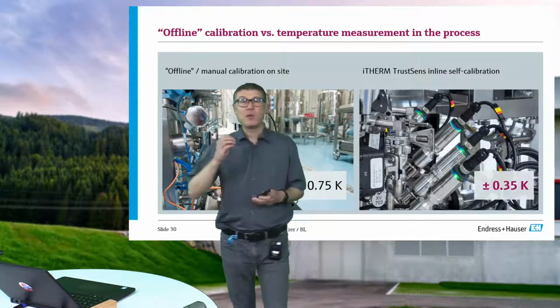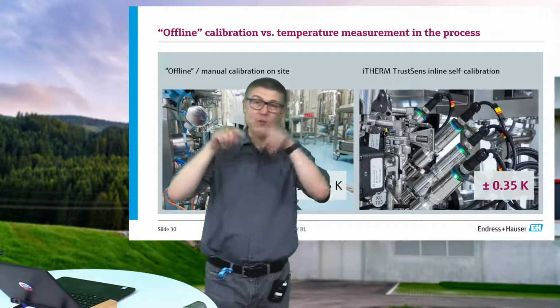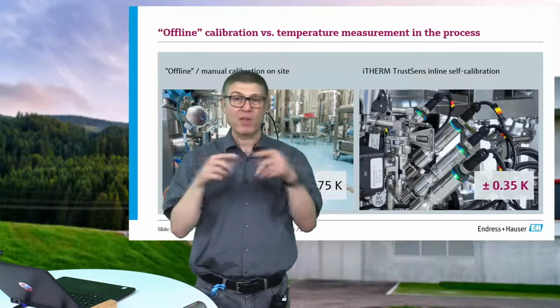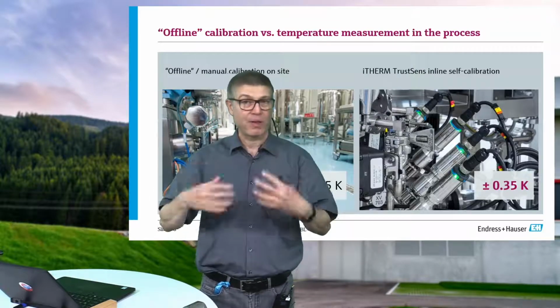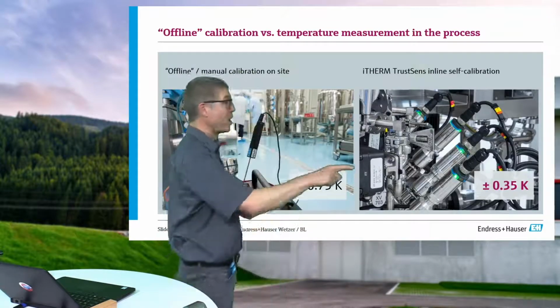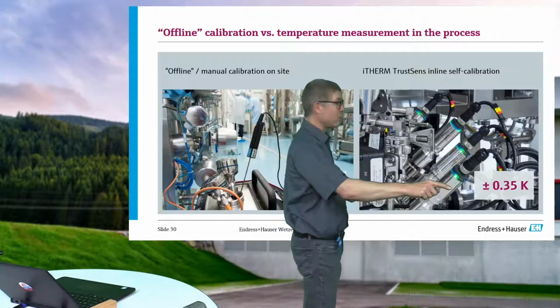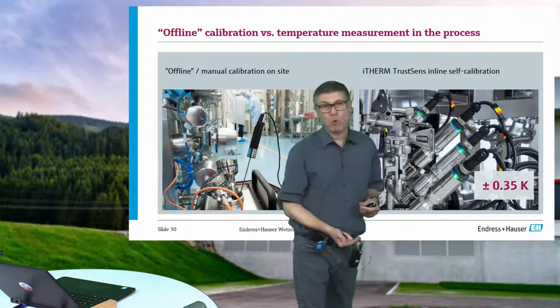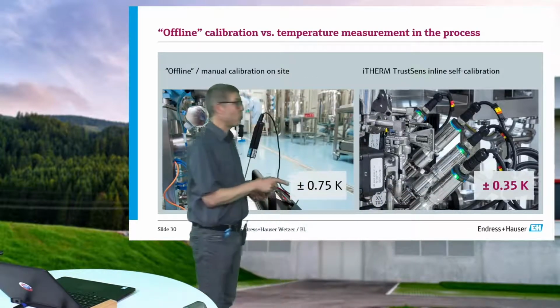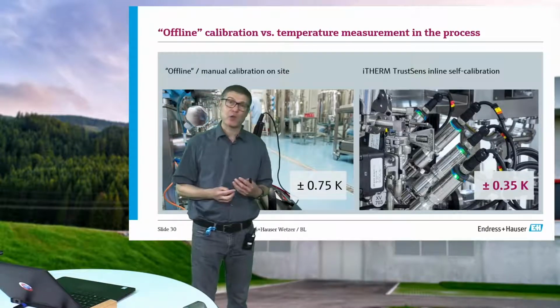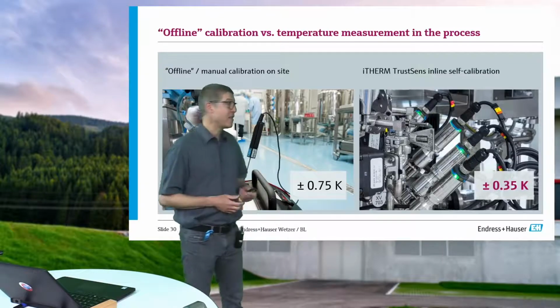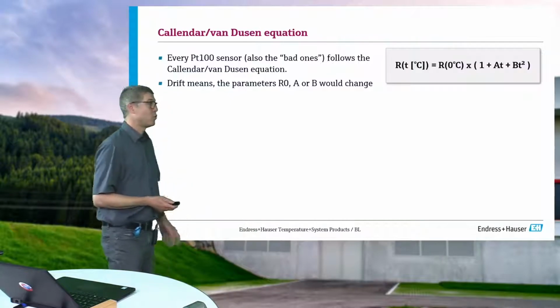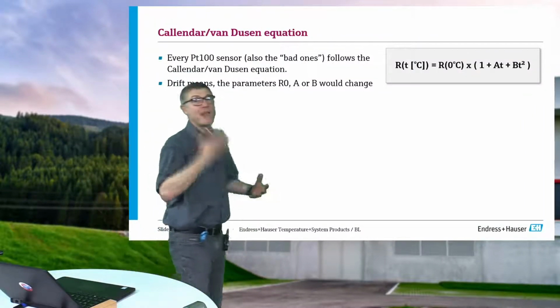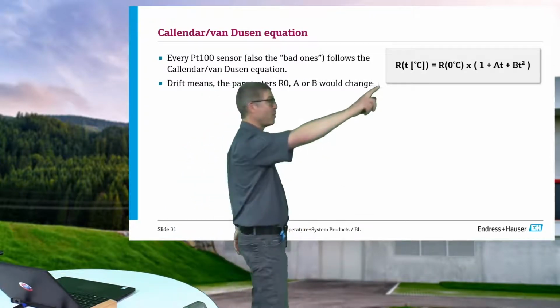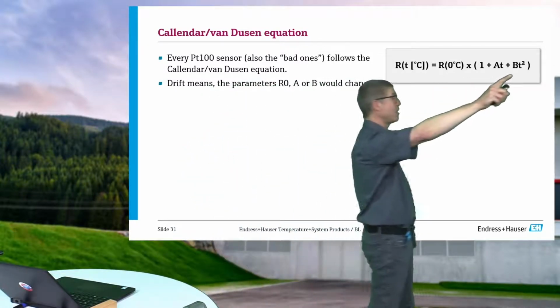0.35. So that means because the reference and the sensor are identically on the same point, there are no influence of heat transfer and whatever. That means we are twice as good at this 1 point than if you do a standard traditional calibration in a dry block calibrator.